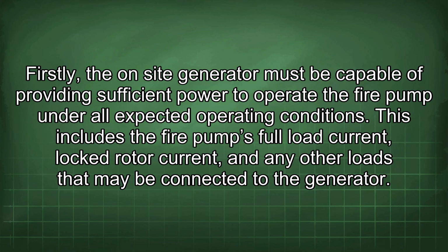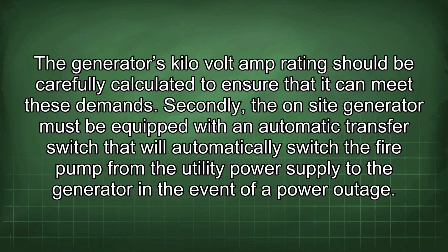Firstly, the on-site generator must be capable of providing sufficient power to operate the fire pump under all expected operating conditions. This includes the fire pump's full load current, locked rotor current, and any other loads that may be connected to the generator. The generator's kilovolt amp rating should be carefully calculated to ensure that it can meet these demands.